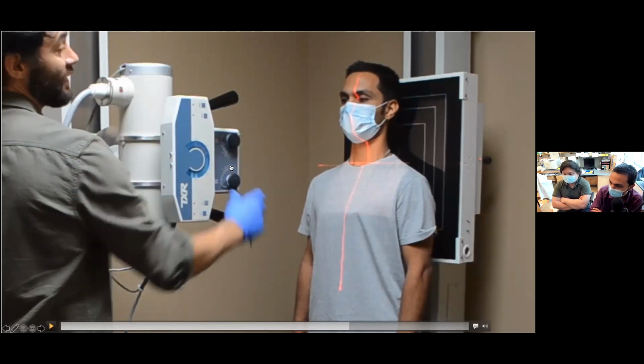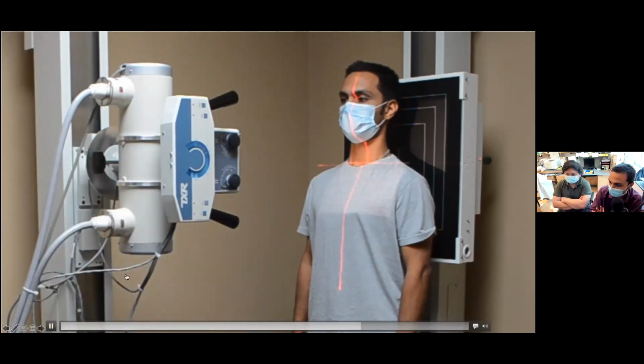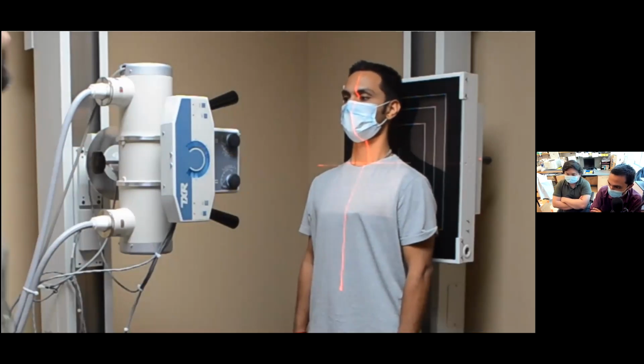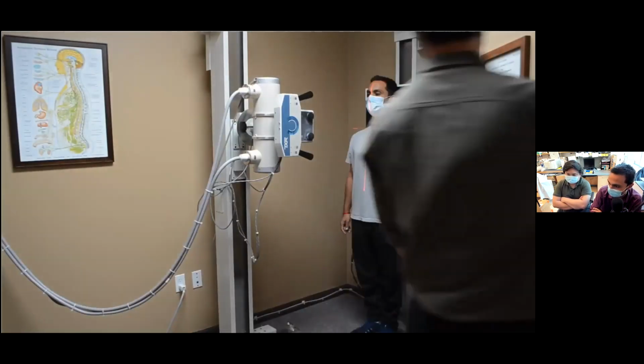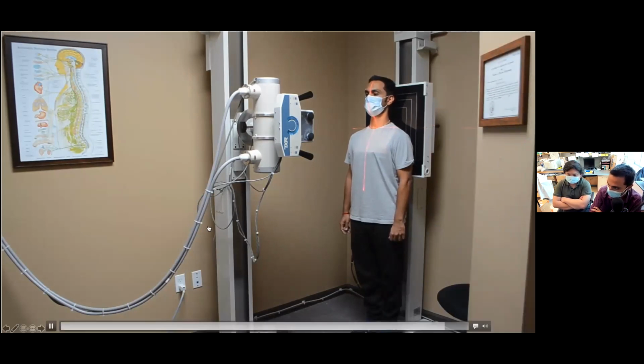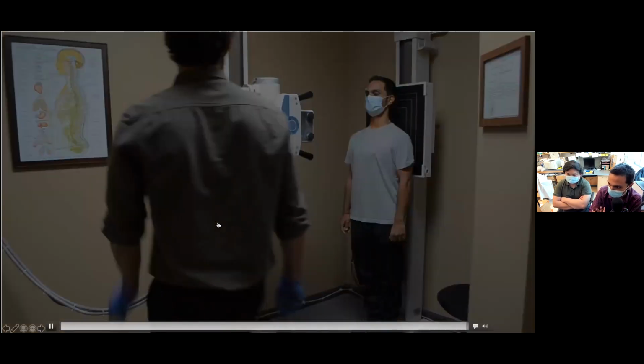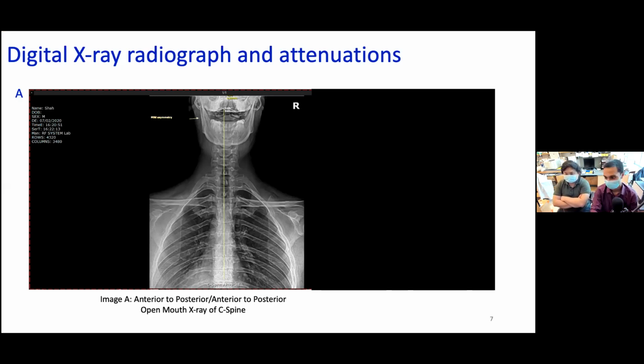And these two knobs here, as you can see, there's a light over me and one behind the detector. That actually helps you regulate the scatter of the X-ray, right? So you can avoid unnecessary radiation, and that way the contrast and the resolution of the X-ray will be perfect. The person goes behind the leaded wall and clicks the button, and then the X-ray radiograph is captured.